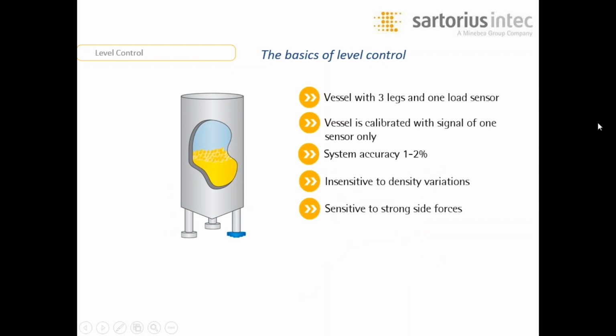Another use of load measuring equipment is the level by weight method of calculating the volume of liquid material in a vessel. And I say liquid. The level by weight functionality is extremely good with a liquid product, but when you get into a dry product, because you can have settling on one side of the tank versus an even dispersion of the product, it's not as accurate. It can still be used, but we wouldn't recommend it for a dry system.